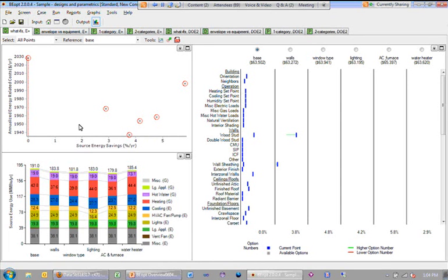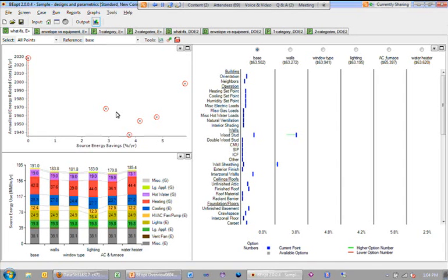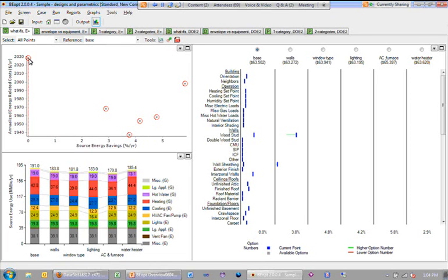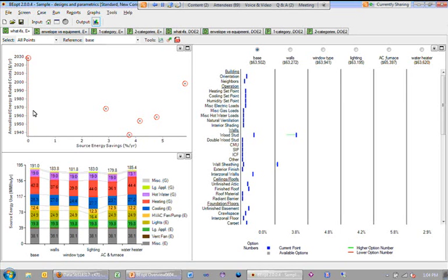Generally speaking, what you'd like to do is, if this is your base building, maybe your standard practice building, and these were a number of different alternative designs that you were evaluating, you'd like to generally be down from this point, which means that you're saving on cost. By saving on cost, I mean that the utility bill savings is going to be greater than the cost of the technology. Perhaps it's rolled into a mortgage or a loan payment. So you have absolute cost savings, and you've got energy savings. You're to the right of this point. So you'd like to be as far down and to the right as possible.